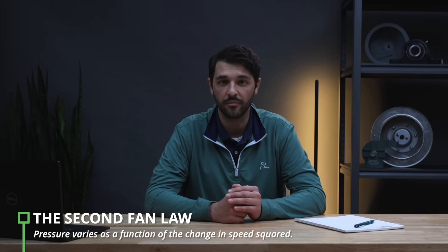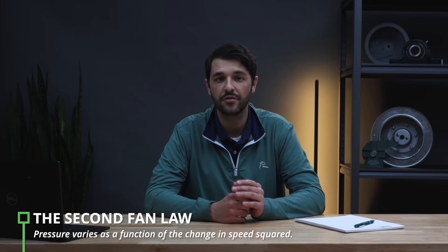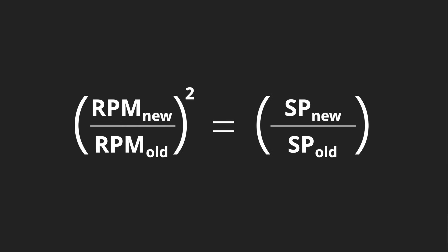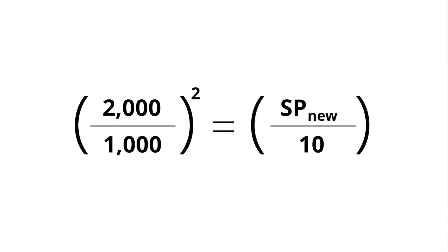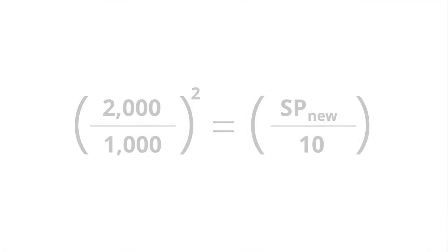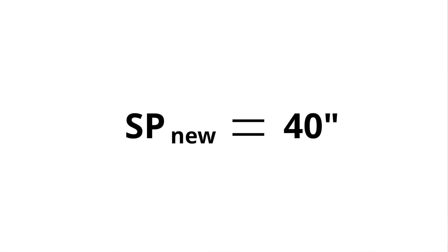The second fan law describes how pressure changes in response to a change in speed. The equation is similar to the first fan law, but here, pressure changes as a function of the change in speed squared, meaning pressure is much more sensitive to a change in speed than flow. Mathematically, the quantity of the change in speed squared equals the change in pressure. Using the same operating point and doubling the speed from 1,000 to 2,000 RPM: the quantity of (2,000 / 1,000) squared equals the new pressure X divided by the old pressure 10 — which solves for a new static pressure of 40 inches of water gauge.